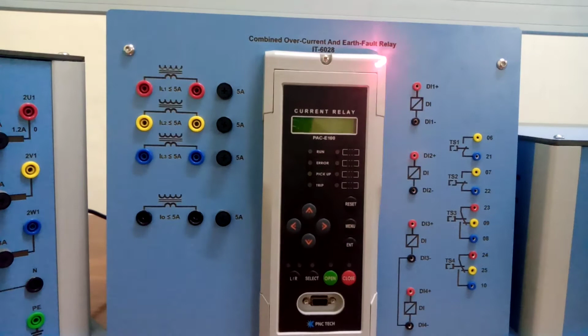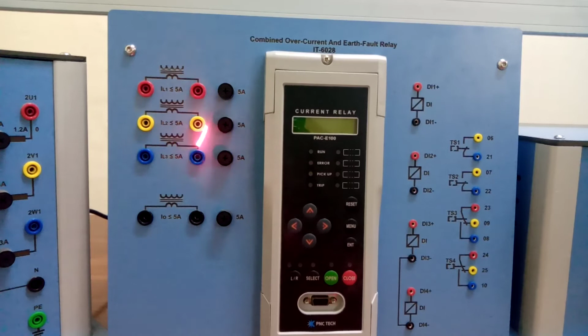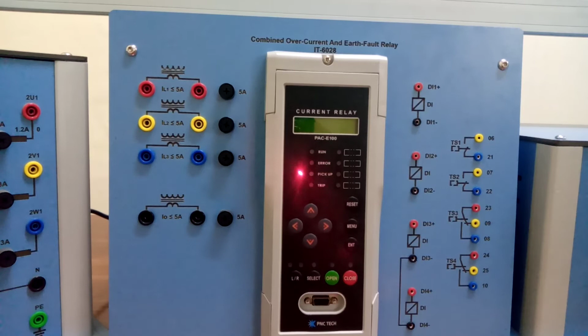This is the combined overcurrent and earth fault relay, and on the left side you can see that there are three phases which are connected in series with your transmission line. Then there is a connection of neutral as well. There are a few fuses for protection, like 5 amperes, so it is recommended that you use this equipment with less than 5 amperes. And then this is your module, and this is a PLC actually. A few selection buttons: reset, menu and entry. Also this is the running condition, like the normal operating condition. Then for the error you will get this line for pickup. If the current is more than the value, this will be a pickup point, and trip will be when the relay operates.